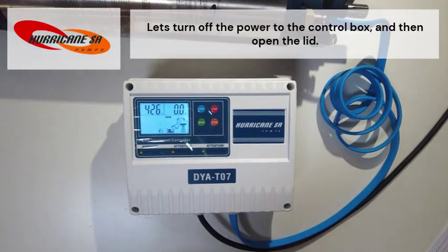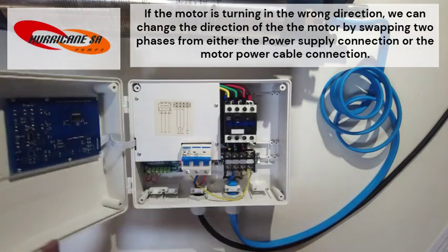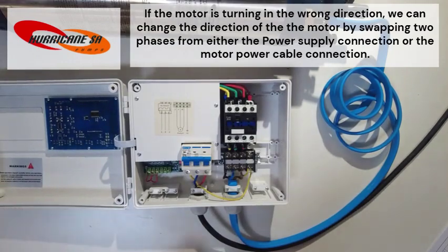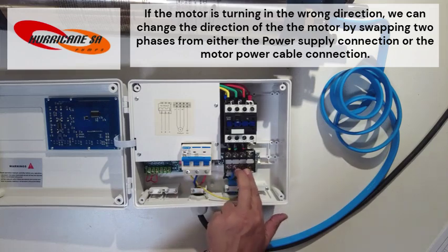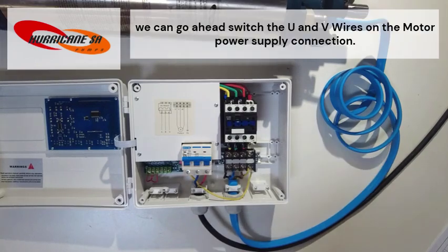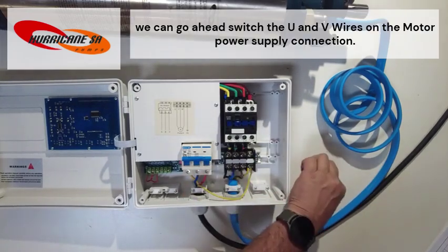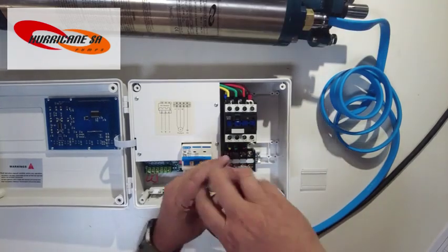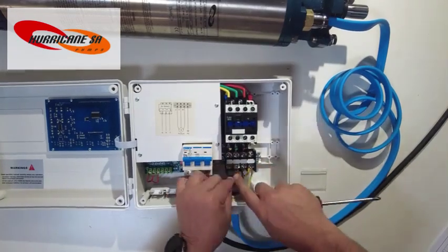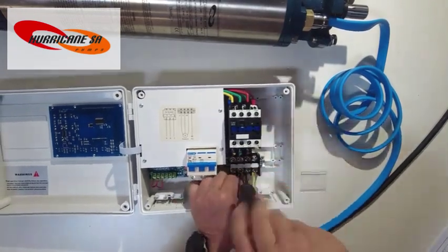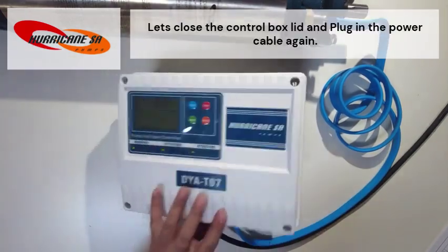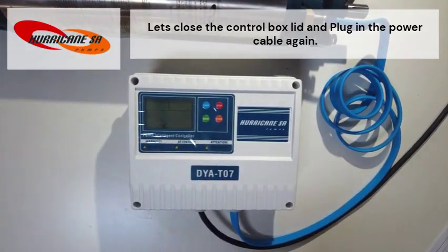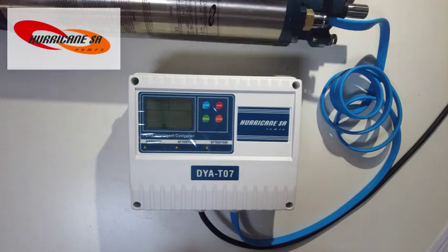Let's turn off the power to the control box and then open the lid. If the motor is turning in the wrong direction, we can change the direction of the motor by swapping 2 phases from either the power supply connection or the motor power cable connection. We can go ahead, switch the U and V wires on the motor power supply connection. Let's close the control box lid and plug in the power cable again.